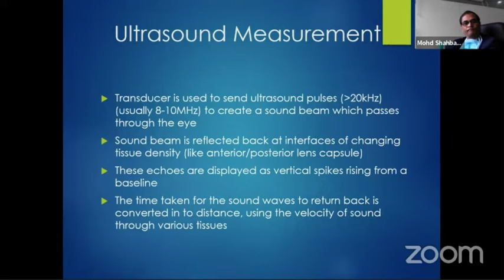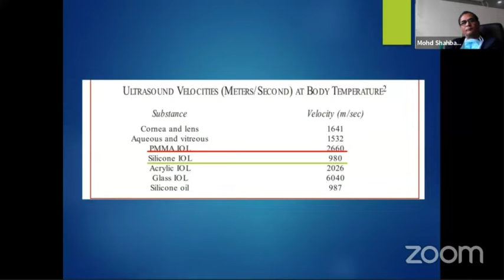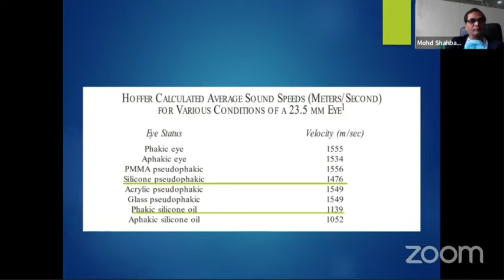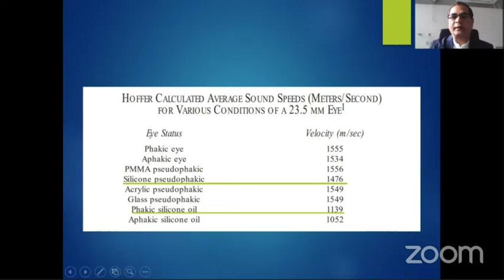The time taken for the sound wave to return is converted into distance using the velocity of sound through the tissue. Now, this is the velocity of sound through the tissue. Why is it important? If you have a PMMA IOL, the velocity will be very high, while if you have a silicone IOL or silicone-filled eye, the velocity is very low. Hoffer calculated average sound speed in meters per second for various conditions of a 23.5 millimeter eye, and he has given a chart we can apply during the measurement.